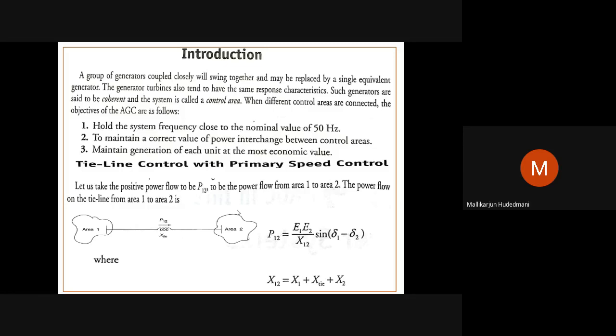It will not check the line frequency. It will just see to it that as and when there is a loading phenomenon by area 2, borrowing power from area 1, definitely P12 becomes a load on area 1. As the load on area 1 increases, naturally the turbine decelerates. When the turbine decelerates, how is the turbine going to cope with the appropriate megawatt exchange, like your point number 2 in the objective? Therefore, the primary loop comes into the picture. The primary loop starts making the valve opening in proportion to that. Therefore, mechanical supplement is given to the turbine to see to it that P12 is addressed. That is how the primary loop comes into the picture.